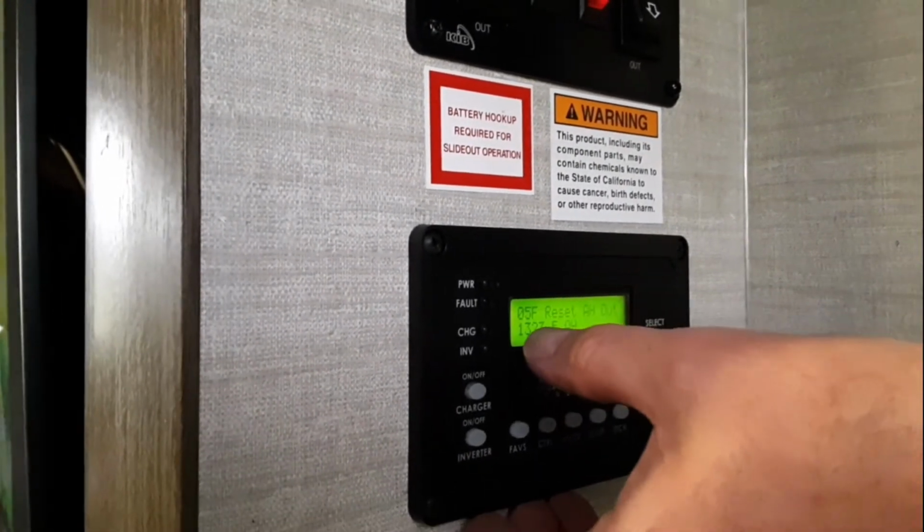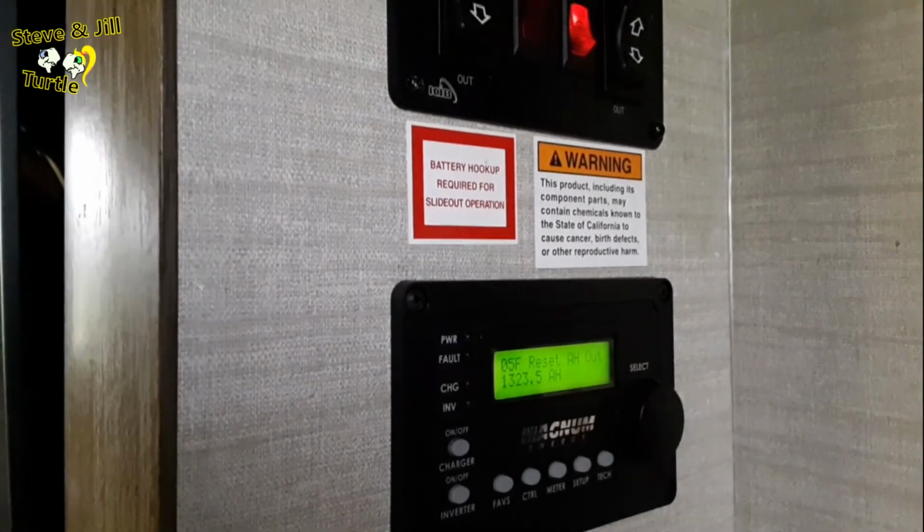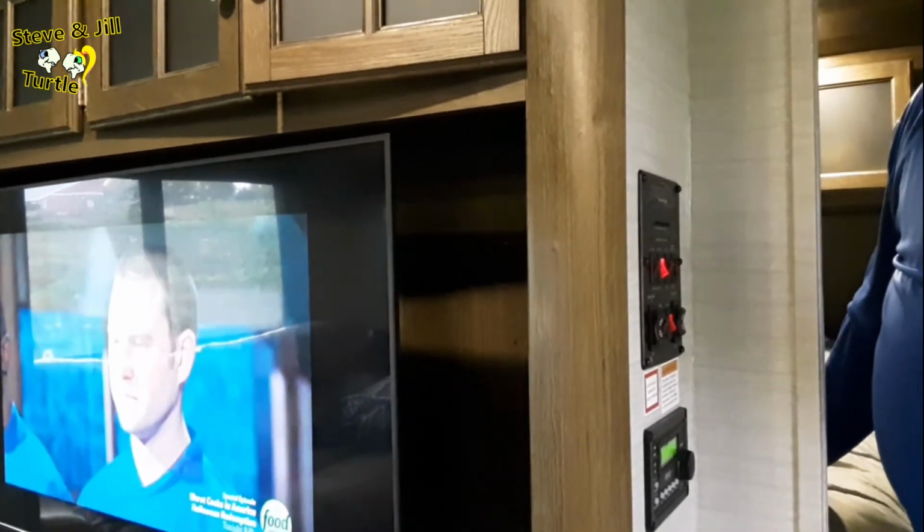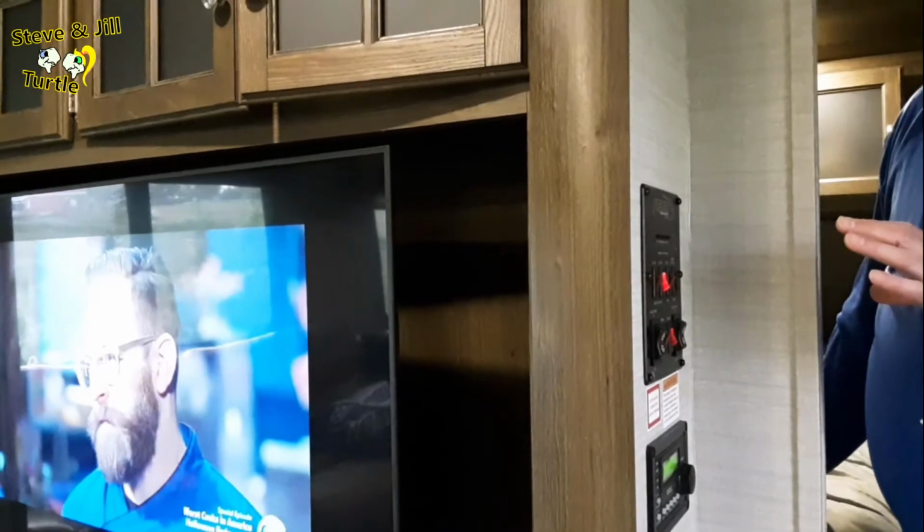My total amp hours out is 1,322. We burn 20 amp hours DC per hour. So it runs around 250 watts, roughly. And roughly, we burn about 6 kilowatts a day, which our solar system recovers. The only downside of any solar system is if you burn more than you use, your battery management system will shut down the batteries to protect themselves, and then you have to manually restart it by jumping from the car.